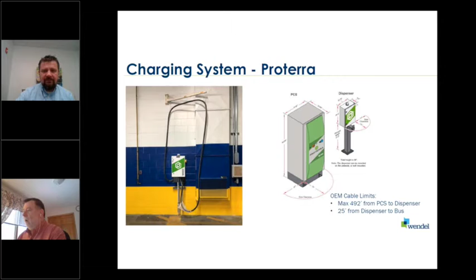hazard. And one other thing that I wanted to bring your attention to is that a lot of the charger dispenser combinations have cable length and equipment distance limitations. You could see for a Proterra charger, it's about 492 feet from the charger to the dispenser, and then about 25 foot from the dispenser to the actual outlet on the bus. We found in our experience that this is pretty close across the board, ABB, Proterra, but there are some variations, and a lot of the manufacturers are willing to work on the cable lengths to be project specific.